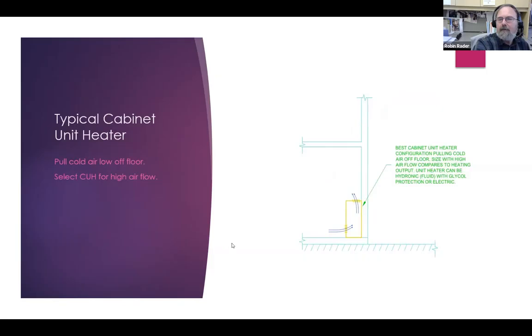So this is a picture of a cabinet unit heater used for entry heating. Note that you pull air into the bottom of the cabinet unit heater and blow it out the top. This sucks the cold air through and warms it. And so this unit heater should have a high flow, should have like a single row coil so that you get a high flow and relatively low delta T out the cabinet unit heater.